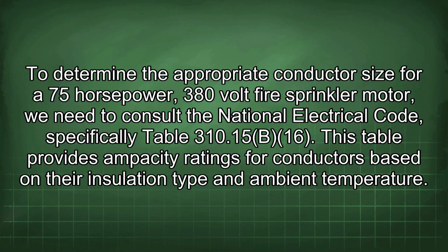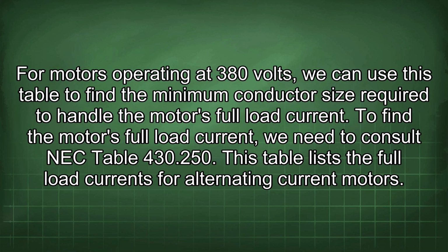To determine the appropriate conductor size for a 75 horsepower, 380 volt fire sprinkler motor, we need to consult the National Electrical Code, specifically Table 310.15(B)(16). This table provides ampacity ratings for conductors based on their insulation type and ambient temperature. For motors operating at 380 volts, we can use this table to find the minimum conductor size required to handle the motor's full load current.